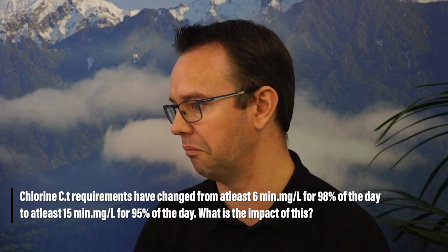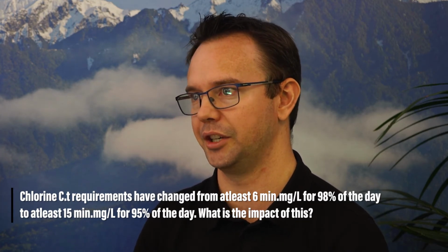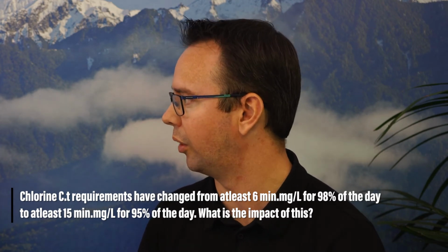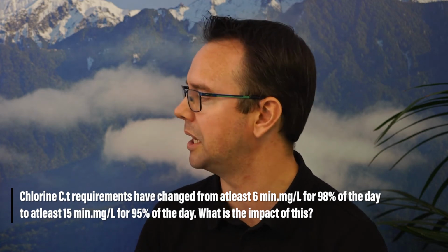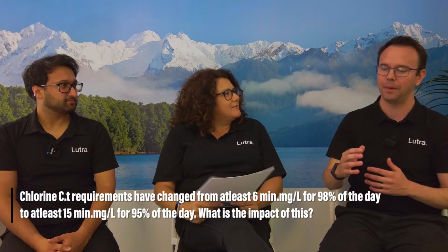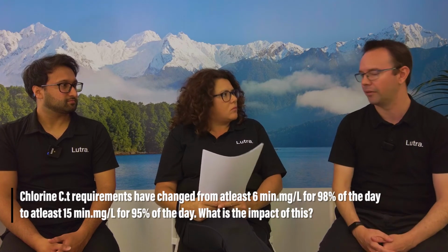You'll be using various methods to demonstrate that. This change is simply changing that number from 6 to 15, so it means more chlorine contact is required. And from a practical perspective, most people will probably be meeting this already. So if you're able to meet the 15 right now, then there's no problem whatsoever.